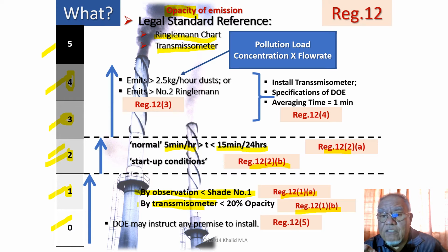So if it is 5 minutes an hour, 24 hours would be many minutes, right? So this law only allows 5 minutes in any 1 hour up to number 2, not number 5, number 2, 5 minutes in 1 hour, but in 24 hours, 15 minutes only. And usually it is allowed during this condition. This is quite common, startup condition.